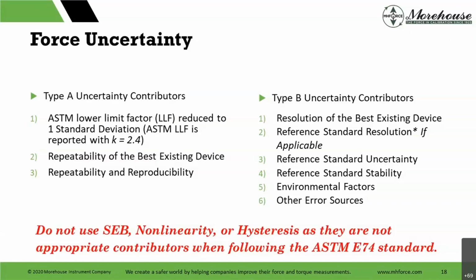That doesn't test for randomization characteristics. That does not test for reproducibility of the standard, where the ASTM uses a statistical method that basically randomizes the conditions of the loading to give the end user an expected performance of that device. You, as the end user, will then derate it using different temperatures, different machines, everything else. But you can capture that in your uncertainty analysis if you follow this.